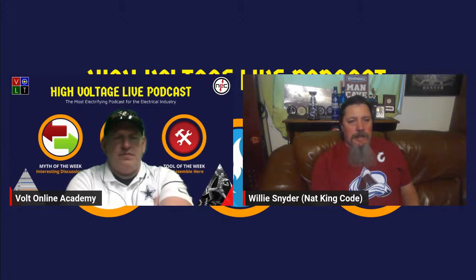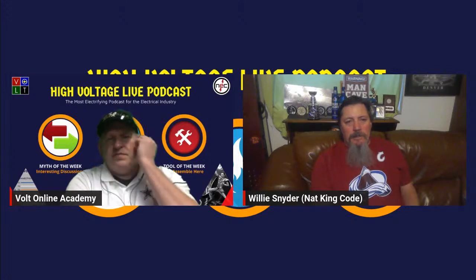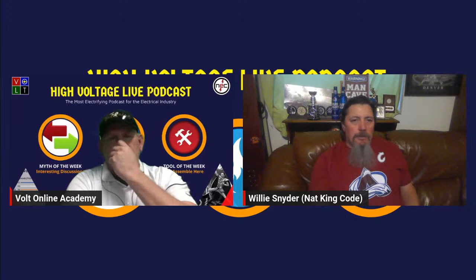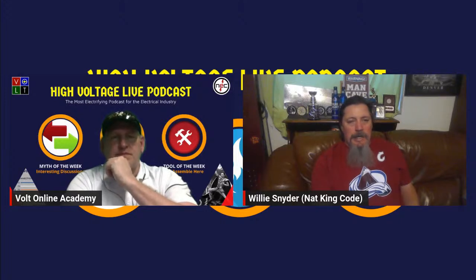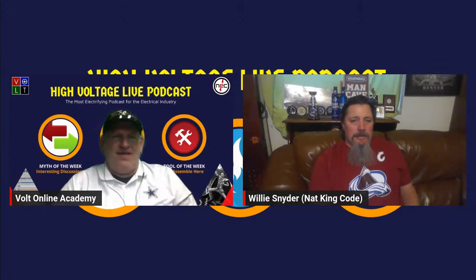So what we have to do as electricians is tell Code-Making Panel 2, hey, is that a rabbit? And then we have to just put it in, because the equipment says that 20 milliamps of personnel protection is compliant for their equipment. So who is Code-Making Panel 2 to come in and say that's not going to save a life, when they have no idea that this is listed, labeled equipment that has been evaluated by a testing agency and proven to be adequate for personnel protection? Who are they to say that 20 milliamps of GFCI protection, or GFPE, whatever it's called, is not adequate for their equipment? Who is Code-Making Panel 2 to say that? It's just wrong. I agree.